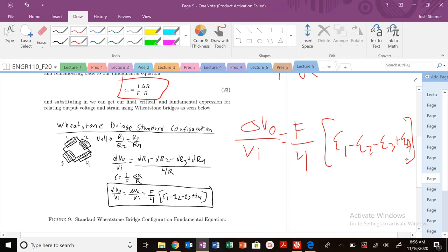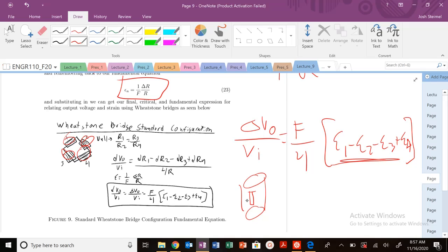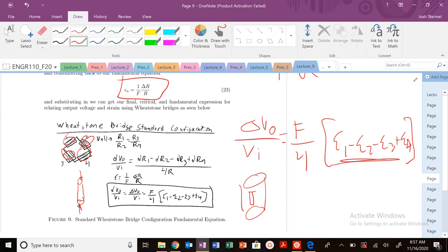Remember, this is the strain measured in each of the strain gauges. Depending on the configuration, we'll be measuring different kinds of strains. We also need to note that our strain gauges are fixed to the surface of a material, so they're only going to measure plane stress or plane strain effectively. We're only going to be able to measure normal strains because we're only measuring if our wire decreases or increases. If we use a strain rosette — a combination of strain gauges — we can figure out our shear strains, and more on that a little bit later.